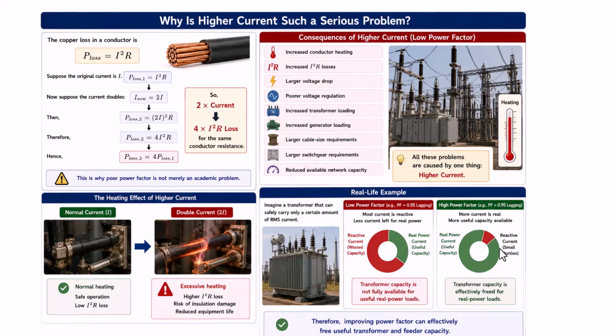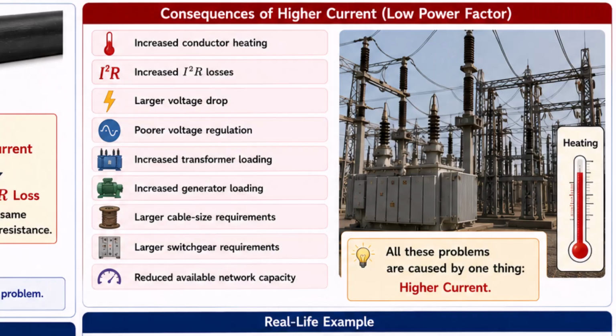So power factor isn't just about a number on a meter. It can directly affect how much current flows and therefore how much energy is lost as heat. This is why poor power factor is not merely an academic problem. Higher current can cause increased conductor heating, increased I square R losses, larger voltage drop, poorer voltage regulation, increased transformer loading, larger cable size requirement, increased generator loading, larger switchgear requirements, and reduced available network capacity.